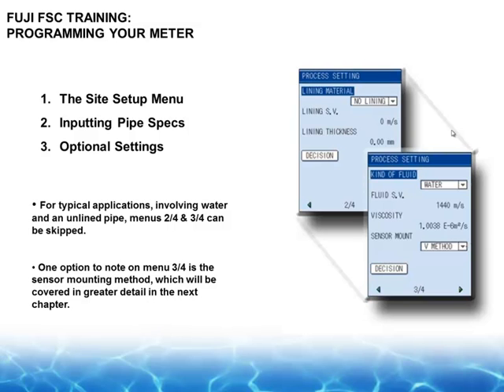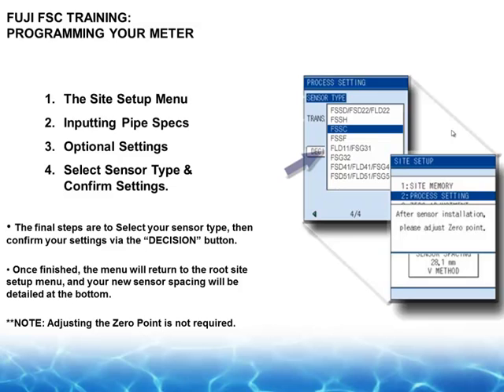You have an exotic proprietary liquid. A good way to shoot for that is to use the specific gravity as a point of reference, or you can contact us. We have people here with really thick pocket protectors and slide rules who like to do bulk modulus equations. So again, we can help you out with something exotic. Moving farther down, you notice the viscosity and other parameters will be predetermined by the drop-down menu. So house rule, we don't adjust the viscosity sensor setting. Sensor mount, in this case, we've selected the V configuration. And then after that, we hit the decision.